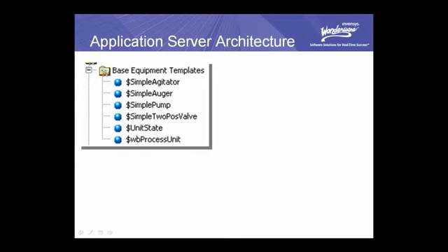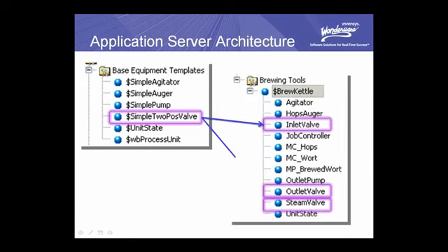This way, we can identify valves that are starting to fail and need rebuilt and schedule maintenance on them before they're used in production again. With the traditional system, this would require us to add the tags and the scripts associated with this ability into our HMI for every single valve. But with Application Server, we can simply modify our valve template, adding the necessary tags, logic, maybe even historizing some of the configuration points, and that change will then get propagated to every valve created from that template.